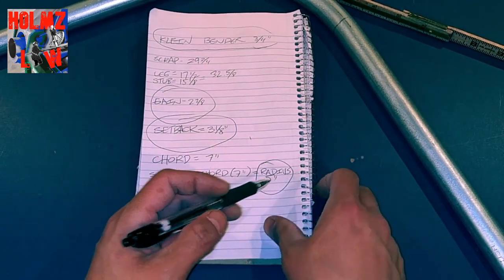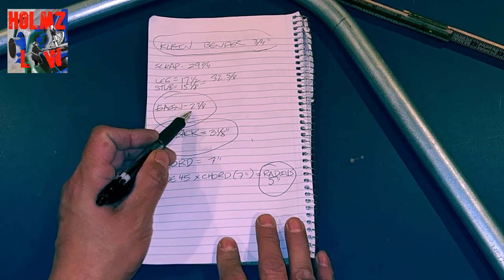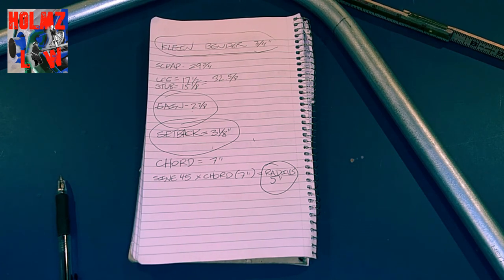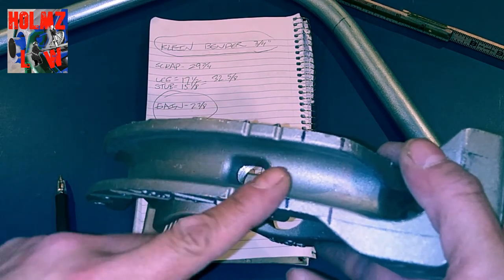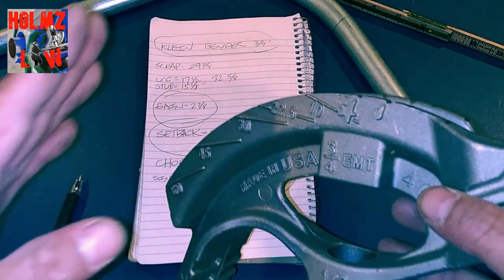So to recap: for the ¾-inch Klein bender, the radius is 5 inches, the setback is 3⅛ inches, the gain is 2⅜ inches, and we have the bender charted for center of bends — a 30-degree mark and a 10-degree mark. That's how you put the center of bend onto your bender for any degree you want, and now you know the setback, gain, and radius for this particular bender.